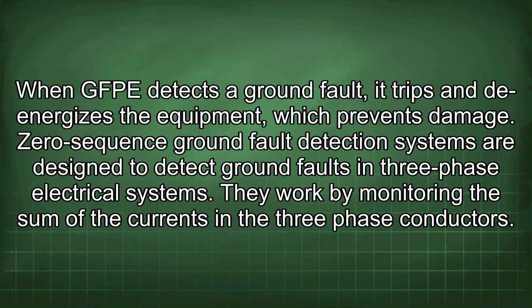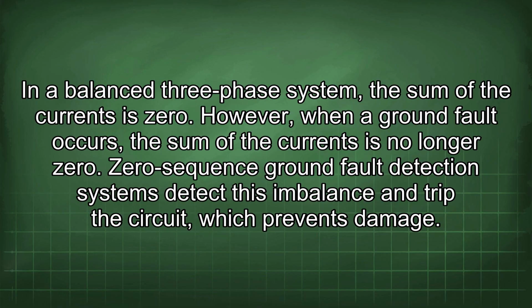Zero-sequence ground fault detection systems are designed to detect ground faults in three-phase electrical systems. They work by monitoring the sum of the currents in the three-phase conductors. In a balanced three-phase system, the sum of the currents is zero. However, when a ground fault occurs, the sum of the currents is no longer zero. Zero-sequence ground fault detection systems detect this imbalance and trip the circuit, which prevents damage.